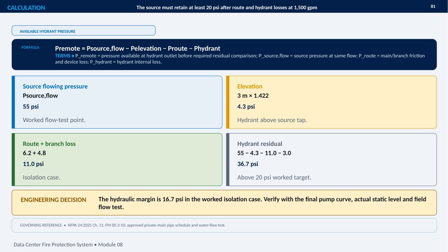Route and branch losses add to 11.0 psi, combining 6.2 and 4.8 psi. Finally, the hydrant internal loss is 3.0 psi. Subtracting those values gives a hydrant residual pressure of 36.7 psi. That is comfortably above the required 20 psi after route and hydrant losses at 1,500 gallons per minute. The resulting hydraulic margin is 16.7 psi.